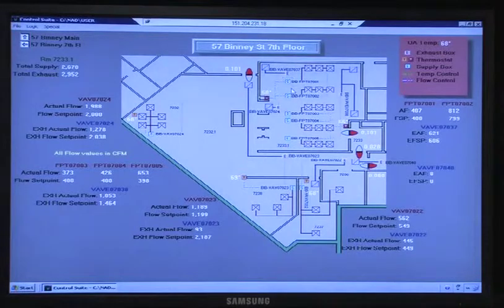So you have one here. You've got another box here. You got another box here. Boxes, so you notice there's a lot of scrubbing going on there because they need to get so many air changes. So when you're doing calculation for air changes in space and pressurization, it's not really happening. It's happening through the fresh air makeup, right?